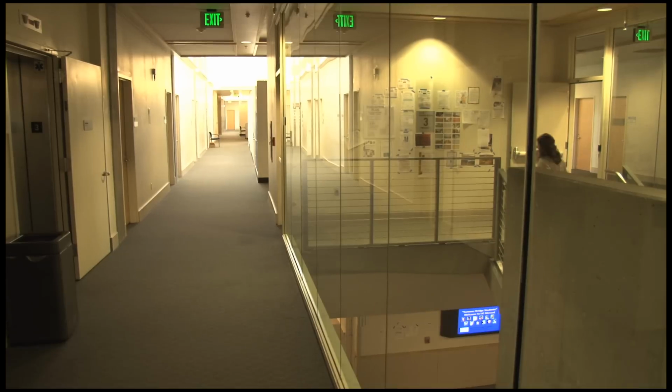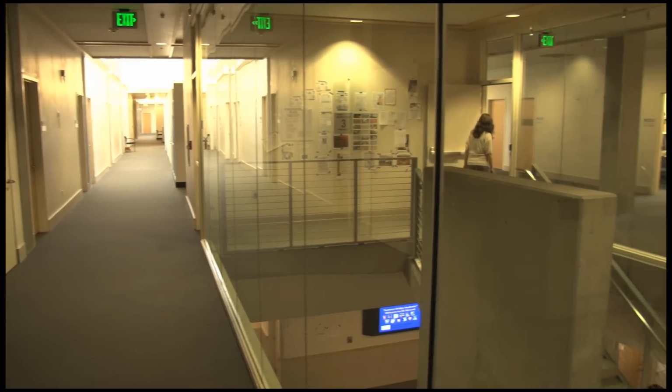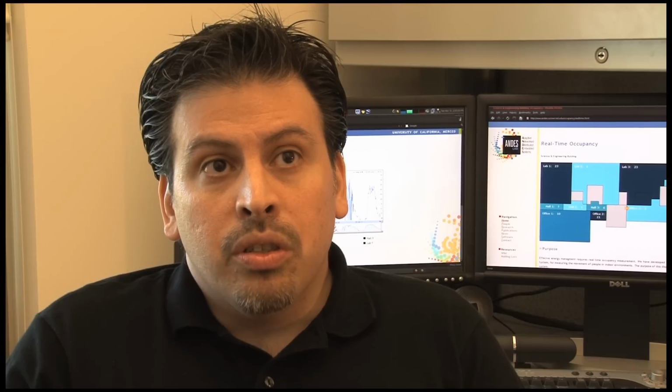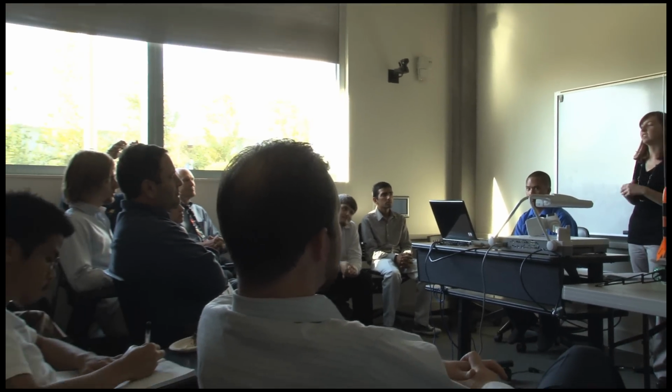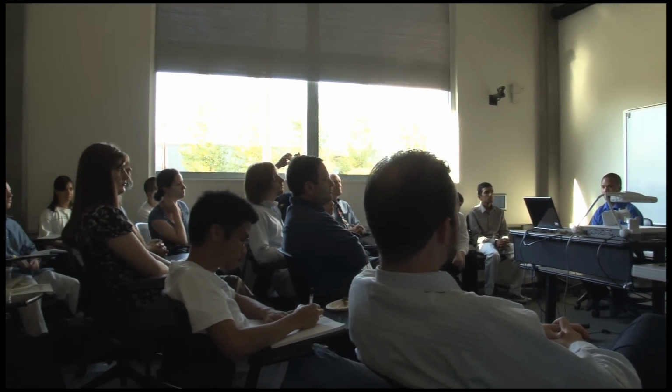The current technology with buildings is essentially, I would say, quite primitive. They assume that people occupy the building during a certain time, let's say from 9 to 5 or from 8 to 6, and they run occupancy, ventilation, and conditioning of rooms based on that schedule. The main issue is that there is no feedback into the system to actually condition the rooms and the ventilation and adapt based on actual occupancy and actual usage.